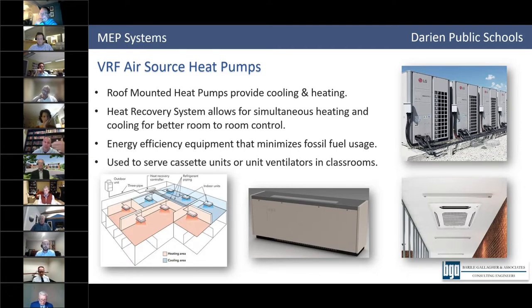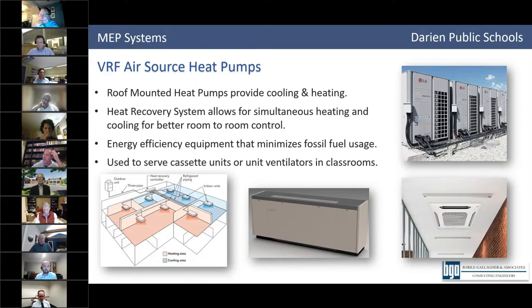Did you look at—I'm sure you did—what were the results when you compared this versus, instead of having 15 or 20 massive units, having basically one of those round conventional systems, a 5-ton heat pump on the roof, just serving each classroom directly? So more one-to-one, if you will. And then finally, putting in some more packaged units and running some ductwork. When you considered those, what were the cost savings, the long-term view on electricity pricing? How did you analyze those three and land on this one?